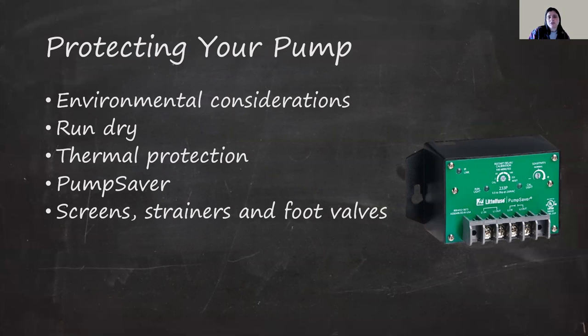A significant limitation of some of the pumps involve whether or not they can run dry. For pumps such as the centrifugal pump, often water is the cooling mechanism to keep the motor from overheating. Without it, the motor will overheat, causing fire hazards or melting of component parts. If you suspect there's a chance your water may run dry, or you'll get a clog in the line preventing flow, I recommend you purchase a pump that is capable of running dry, such as the peristaltic or diaphragm, or implement other safety mechanisms to protect your pump.